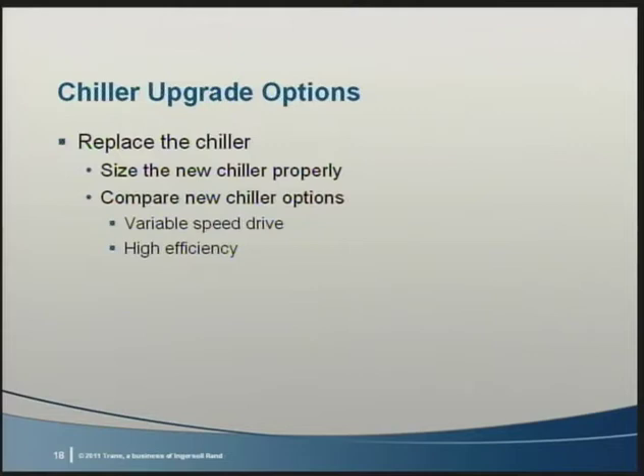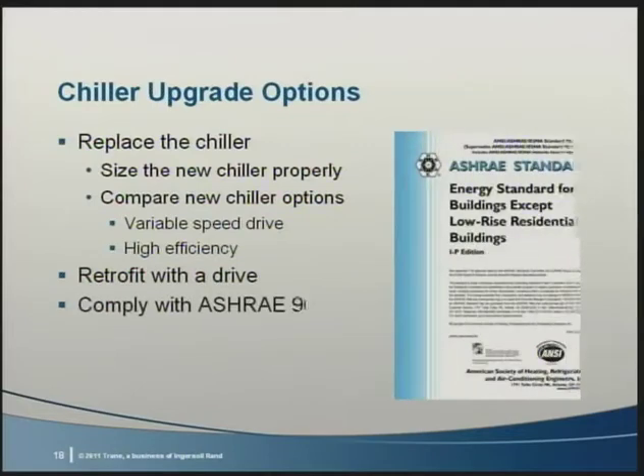Let's start with the chiller. Two options to consider are replacing or retrofitting the chiller. In some cases, the chiller may be older and ready for replacement. We'll discuss the importance of sizing the new chiller properly and also examine two similarly priced chillers. In either case, we need to make sure that the replacement chiller complies with ASHRAE 90.1 requirements, on which the local codes are often set.